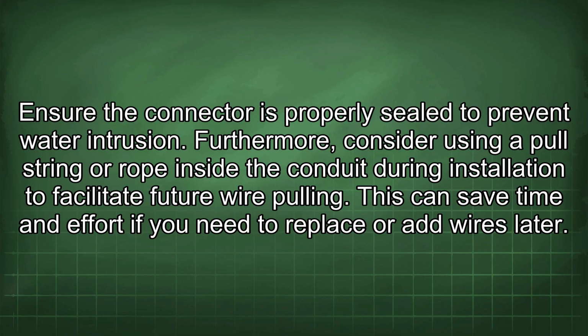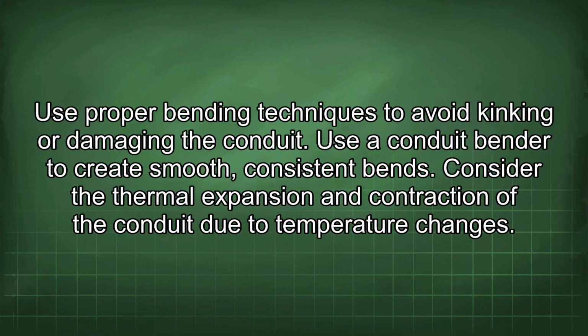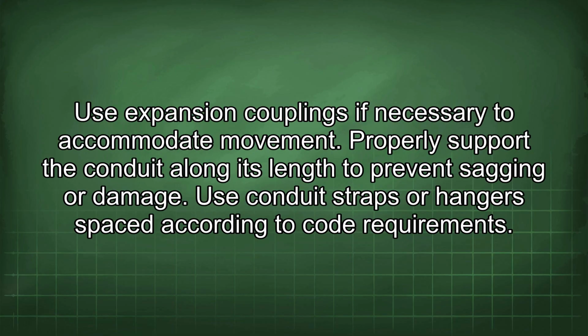Furthermore, consider using a pull string or rope inside the conduit during installation to facilitate future wire pulling. This can save time and effort if you need to replace or add wires later. Use proper bending techniques to avoid kinking or damaging the conduit. Use a conduit bender to create smooth, consistent bends. Consider the thermal expansion and contraction of the conduit due to temperature changes. Use expansion couplings if necessary to accommodate movement.